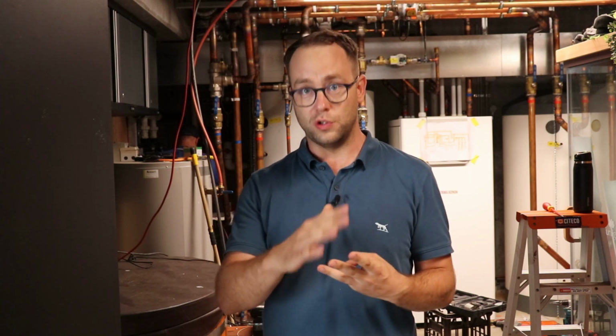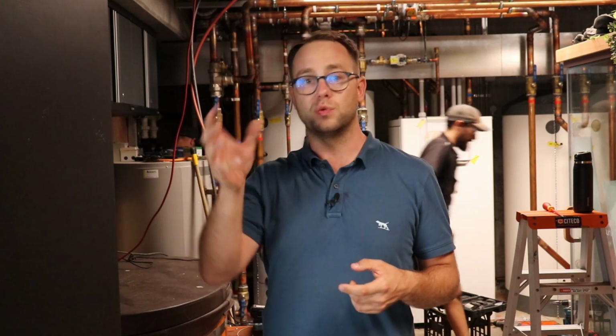And they've called us to come in, and we did an assessment, and we actually found out that there was a lot of problems, but I'll talk to you about the three main problems right now. So one of the problems was that there's a lot of valves which move, which divert water either one way or another way, or they might mix water, say sending 70% of the water this way and 30% of the water that way, to regulate temperatures or to send the exact amount of energy we need somewhere.